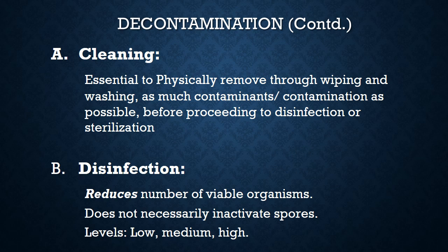So the idea is that you don't take an instrument contaminated with dried blood or fecal matter or pus, and put it in an autoclave to sterilize it, because the bacterial load and the coating on that instrument may be thick enough to prevent sterilization and may ultimately cause cross contamination.